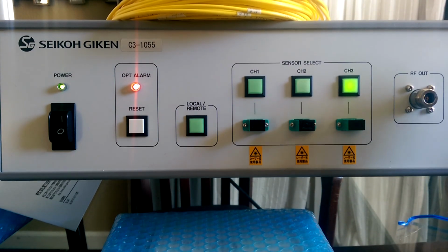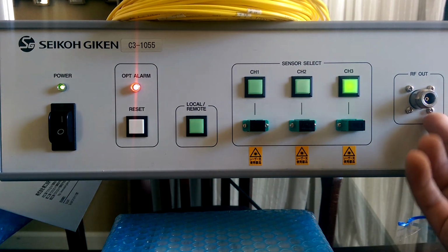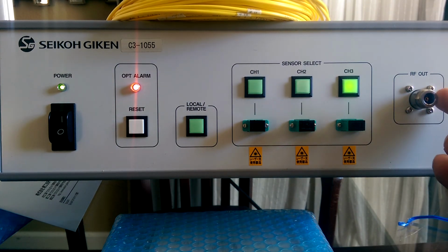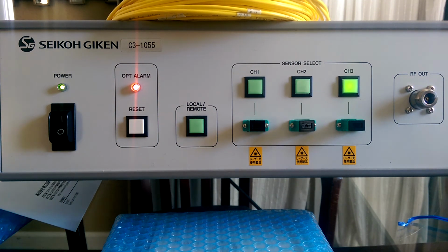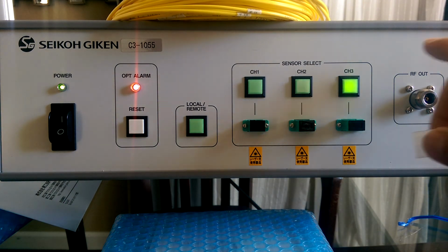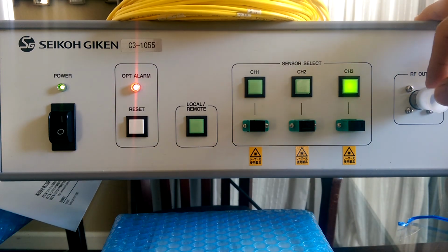Now on to the RF out. This is a standard 50 ohm output to your measuring device. You'd hook up a phase stable cable directly from here to your spectrum analyzer, network analyzer, or oscilloscope - whatever measuring equipment you're using, as long as it has a 50 ohm input. This is going to be your source.